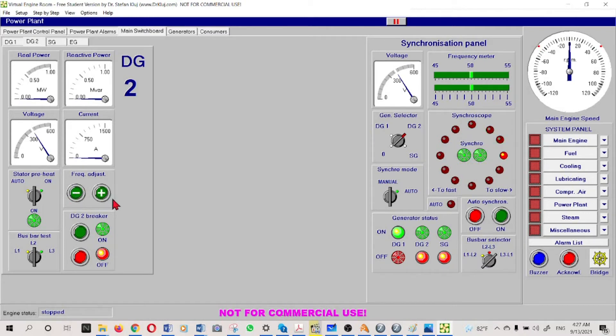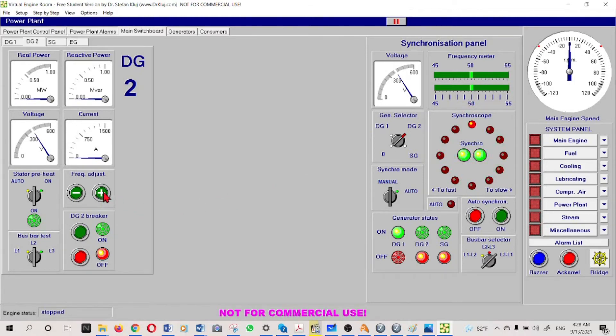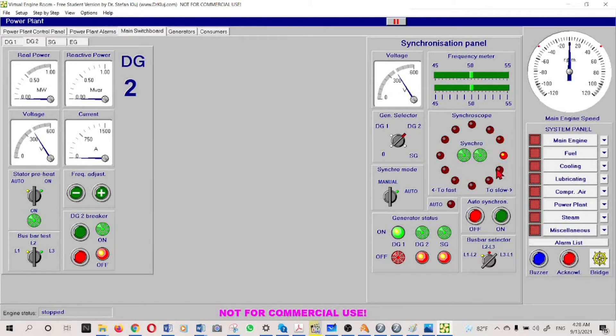I can adjust the wheel - it's dropping back to 50 and further reducing. In one instant it starts to move into anti-clockwise direction, which means now the incoming generator speed is slightly less. But as we know, we need slightly higher RPM, so now again I'll speed up - I'll increase this.